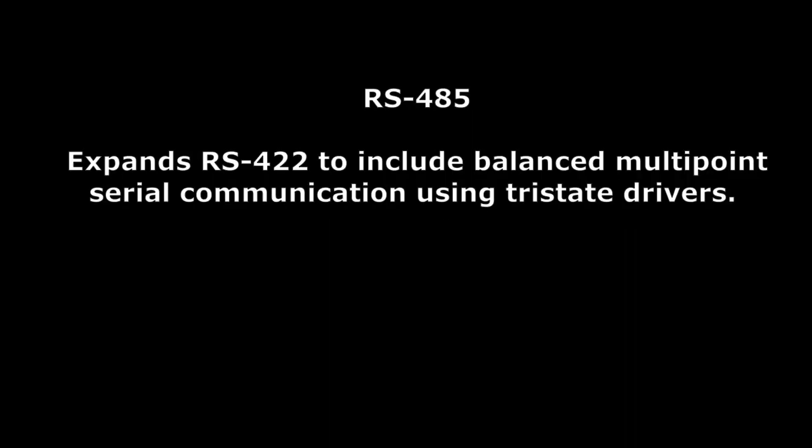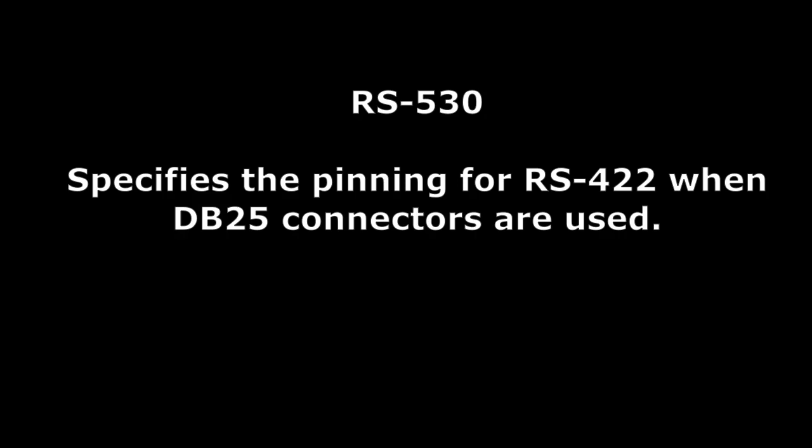RS-485 expands RS-422 to include balanced multipoint serial communication using tri-state drivers. RS-530 specifies the pinning for RS-422 when DB25 connectors are used. Note that RS-530 cables look like RS-232 cables but are not compatible with them.